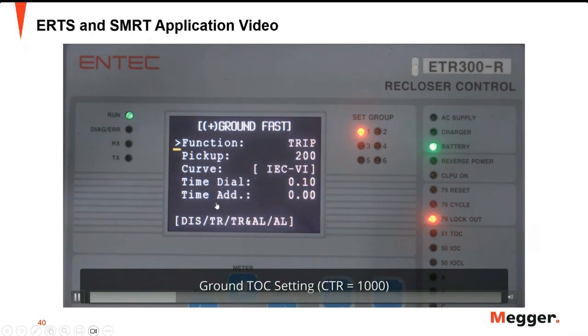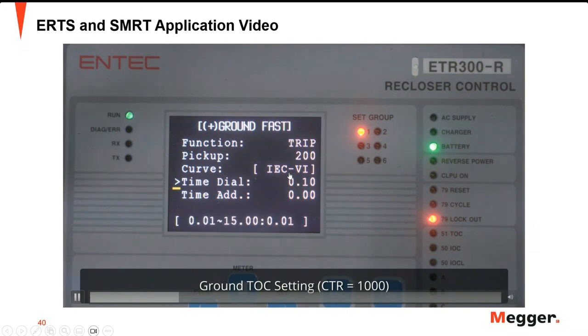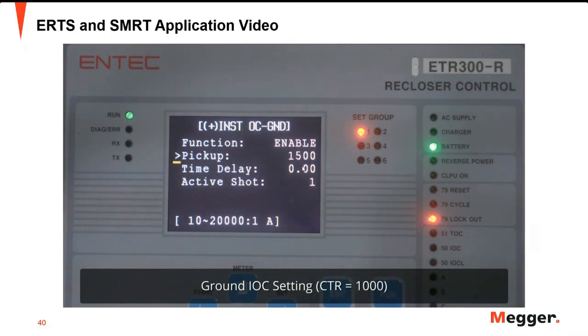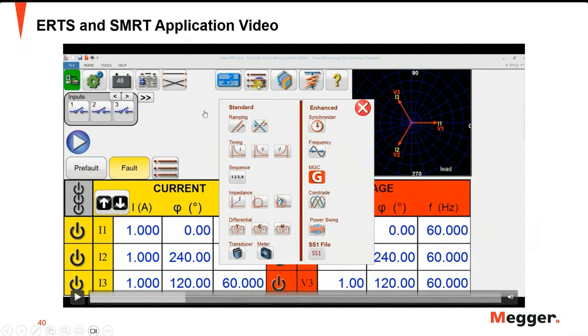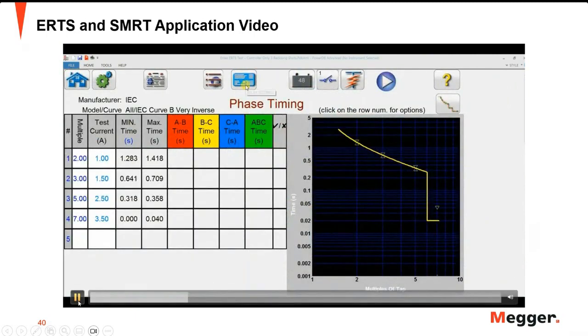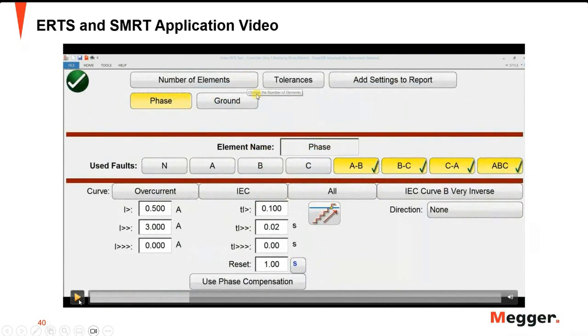Next, we'll check the settings so that we can decide our test currents. This is very important when testing protection functions. We use the overcurrent module in the RTMS software. Here in the settings for the overcurrent — this is for secondary injection only. We are using a current reflected on the secondary side. In our settings the ratio is 1000:1 and the settings for the overcurrent are 500. That's why we put 0.5 here as the pickup setting.